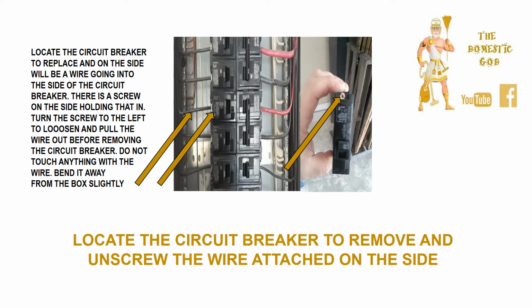Locate the circuit breaker to remove and unscrew the wire attached on the side. Locate the circuit breaker that you're going to replace, and on the side will be a wire going into the side of the circuit breaker. There is a screw on the side holding that in. Turn the screw to the left to loosen and pull the wire out before removing the circuit breaker. Do not touch anything with the exposed wire. Bend it away from the box slightly.